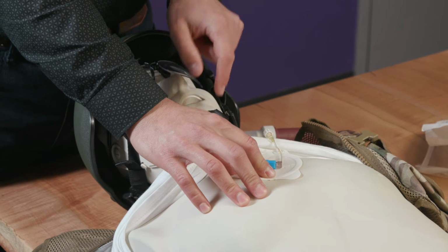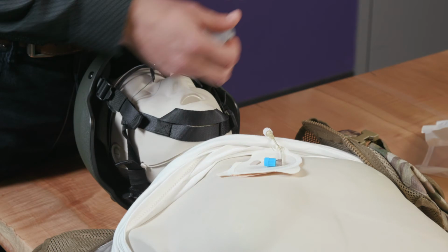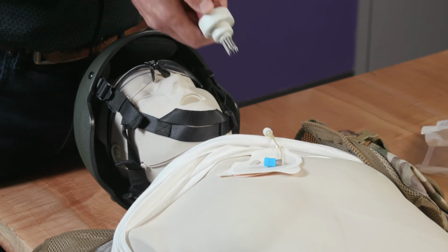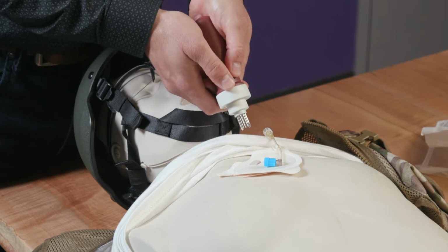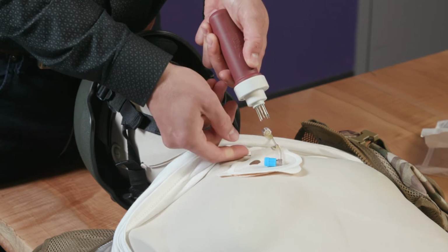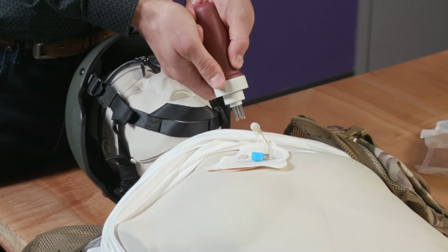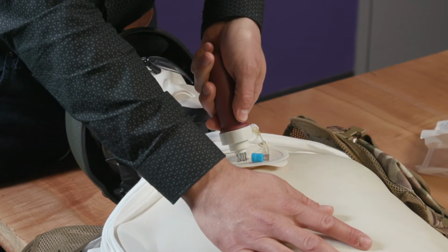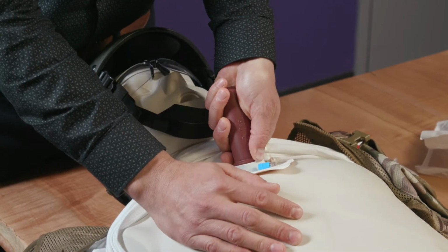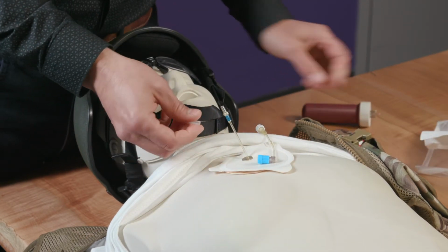So you're going to do that, and that tells you where you need to put your actual incision site. Once you've got that stuck on there, then you take your actual device, pull the cap off, and then you're ready to go. Some of the key things that they told us is perpendicularity with this device is very important. If you don't get perpendicularity, you're going to have trouble with a full deployment. So just to prevent my model from sliding, I'm going to put my hand here, but in actuality you would probably want to do this with two hands. And then you push until you feel that thump.